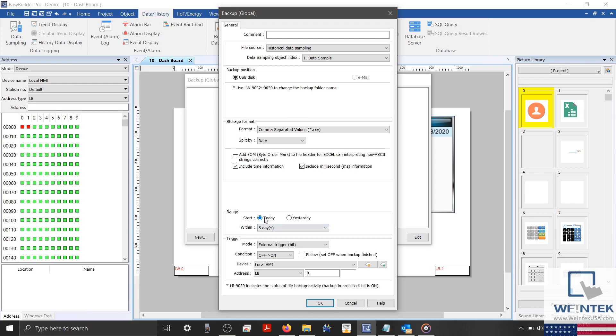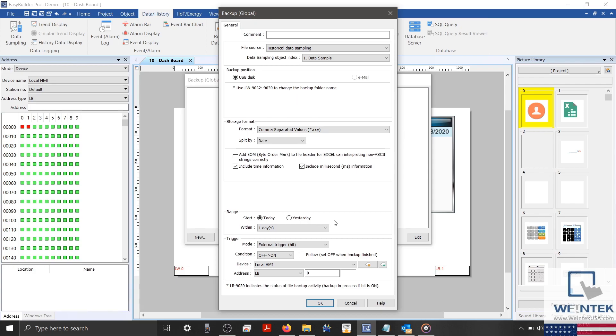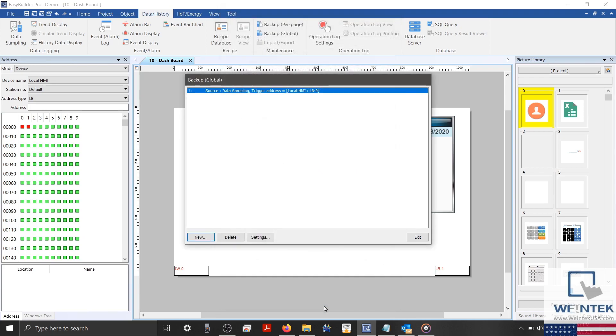I'm going to set our Start Time to Today, and configure our Range to 1. This will ensure that the latest 1 file is saved. I'd like to note that the Range configured works in tandem with the preservation limit. For example, our Data Sampling object will preserve data from the current day, as well as data logged the day before. If within our application we configured the backup range to 2, our Data Log would be split by date, and our HMI will export 2 separate CSV files. At the bottom, we'll leave our Bit Trigger configured to LB0, and I'll click OK to close our Backup object.